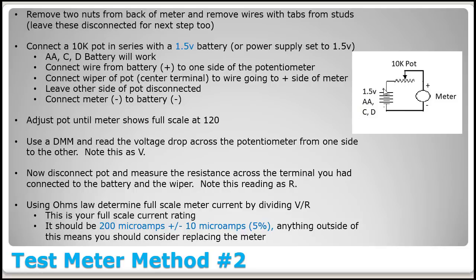Next, disconnect the battery here, or the power supply, and then flip your meter over to resistance reading instead of volts, and measure the resistance from here to here, and write that value down as R. Then we're basically going to use Ohm's law: V divided by R, and that should give you your full scale current meter rating. This result should be around 200 microamps, because that's what this meter is rated at, plus or minus 10 microamps. That would give you a 5% tolerance. Anything more than that, you should consider replacing this meter.